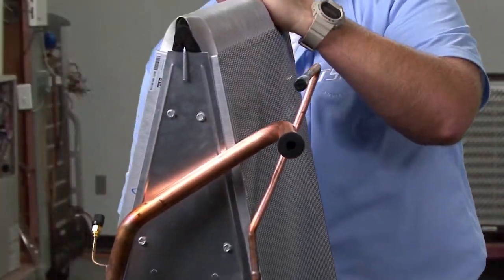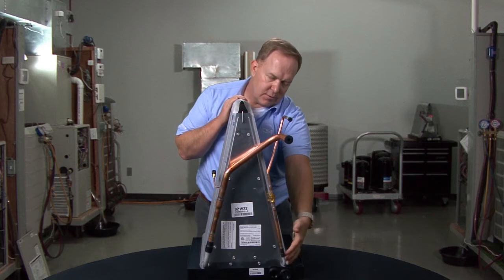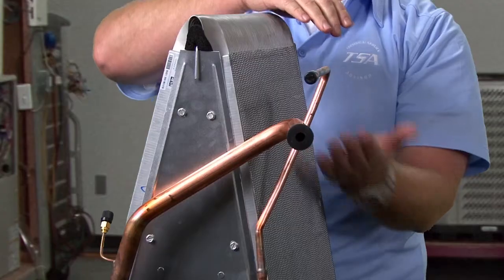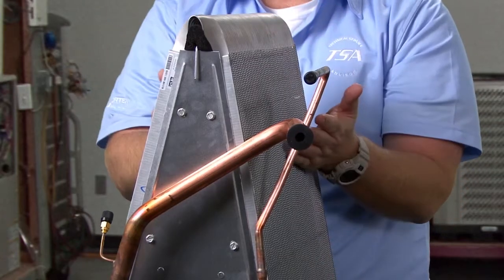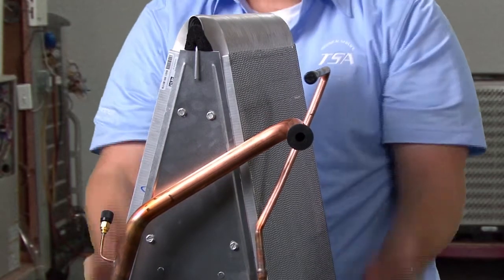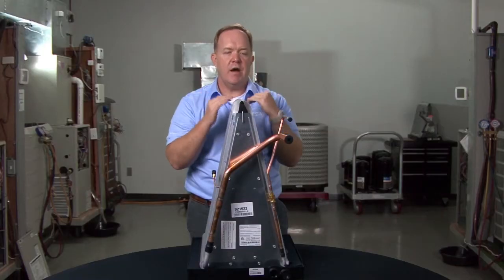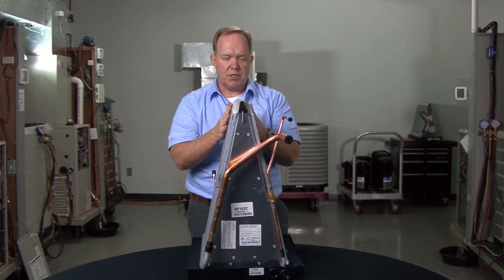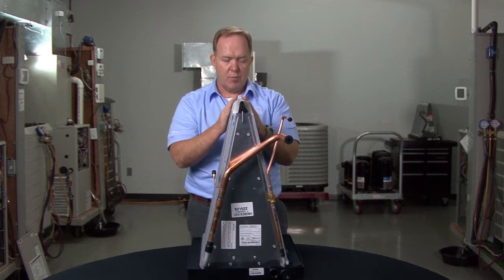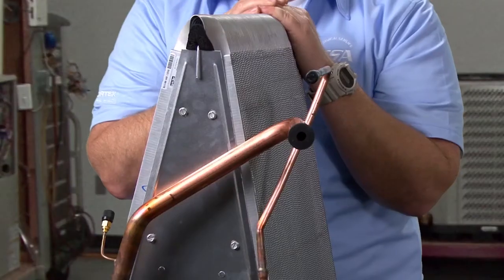When the system is active and the condenser is operating, you've got your liquid inlet down through the liquid line distributor into the liquid header. These coils will then begin to fill almost like a glass of water, where you have this cascade effect from one side down to the opposite side. That also helps to improve their performance because you don't have multiple circuits that you're trying to saturate on two individual slabs like you would with a traditional copper fin and tube coil — that's another point of superiority of this technology over the aging copper fin and tube designs.